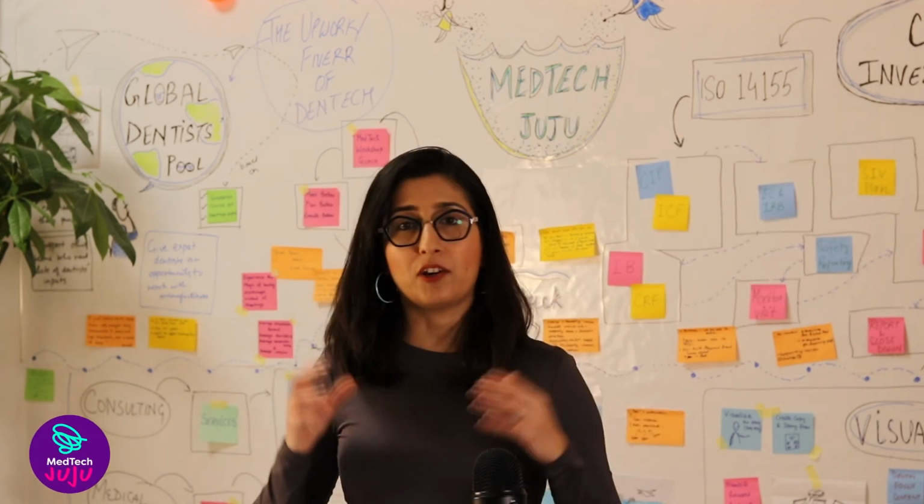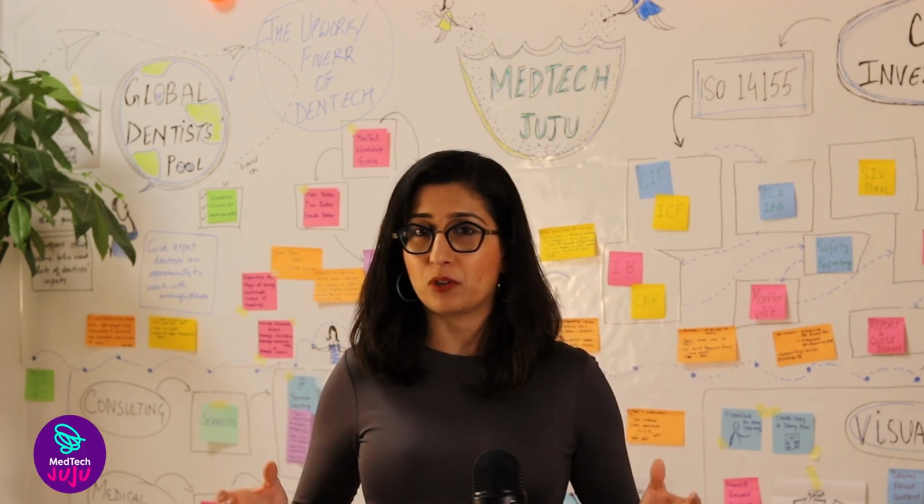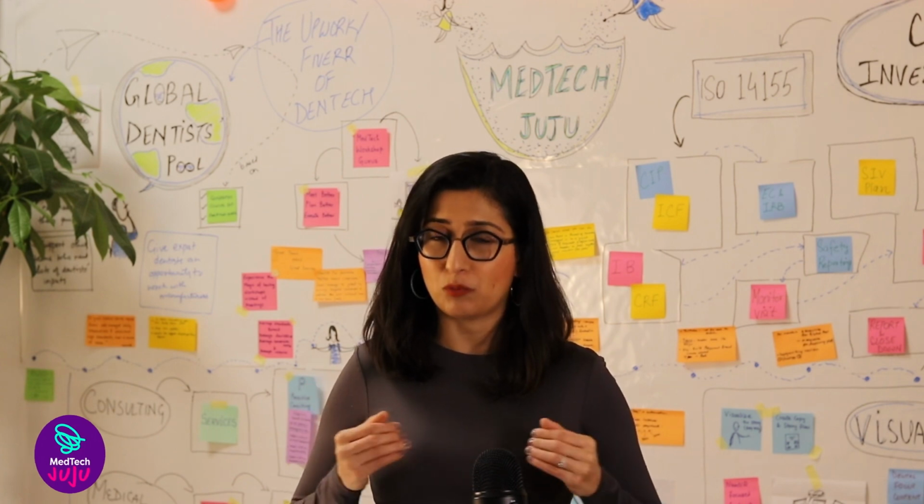In Europe, it's called ISO 13485, and in the States, it's different. There are standards that are followed to set up this QMS depending on which region you're setting up your company in. And it's usually a good idea to start thinking about your quality management system right at the get-go.